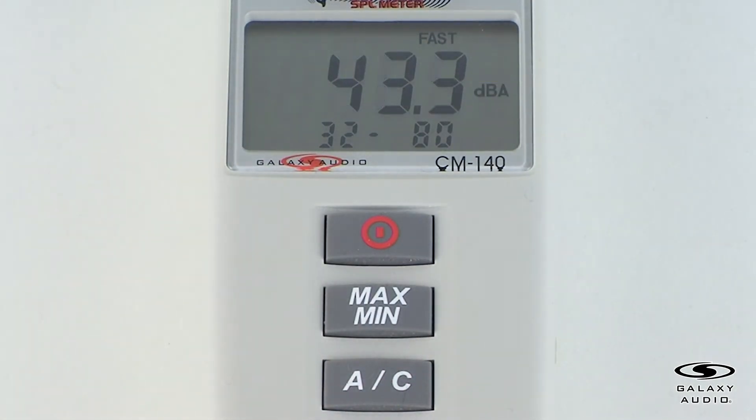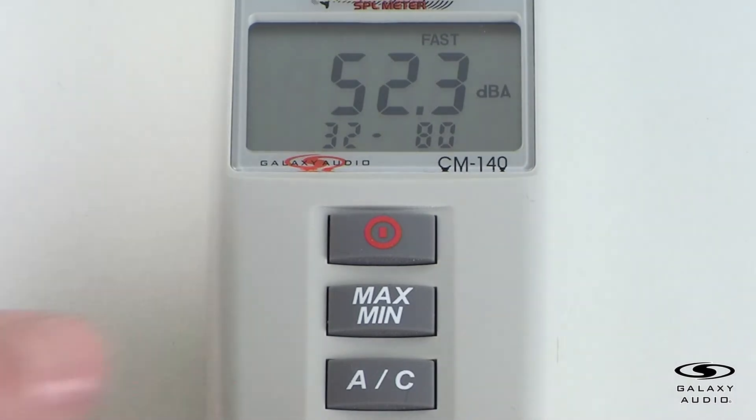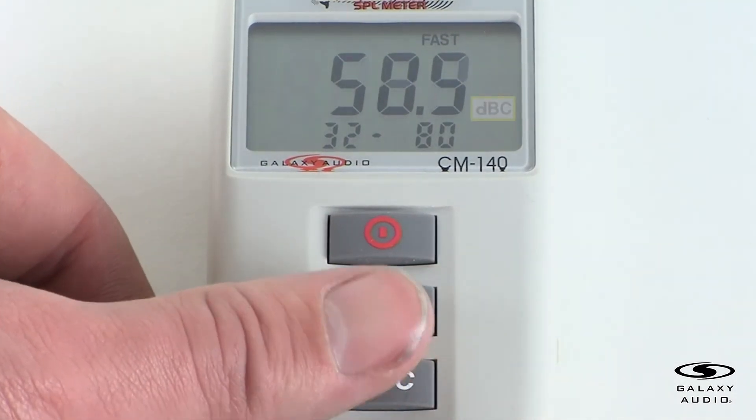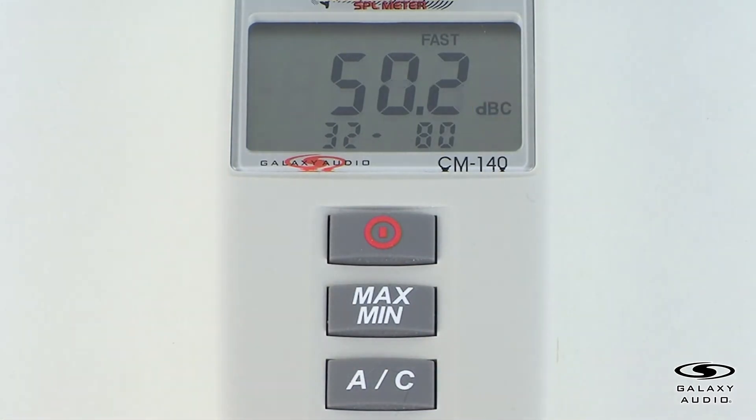When measuring sounds that have a large low-frequency component or consistently above 95 decibels, such as live music or machinery, use the C weighting setting. If the C-weighted level is much higher than the A-weighted level, there will be a large amount of low-frequency content.